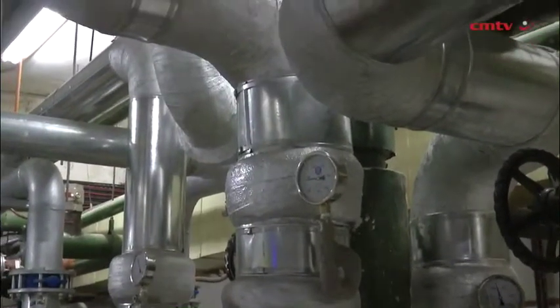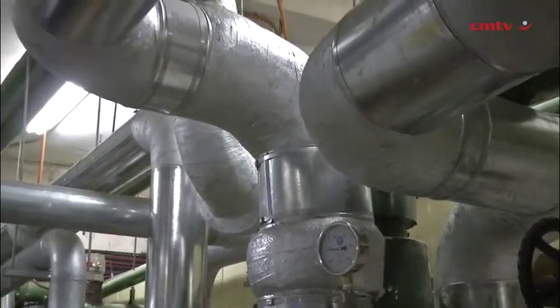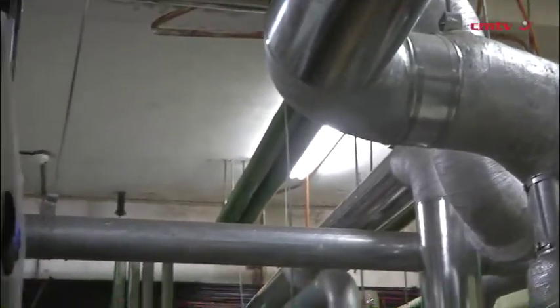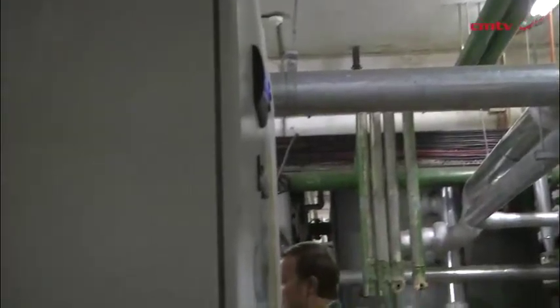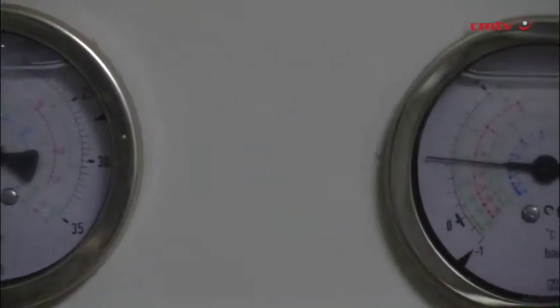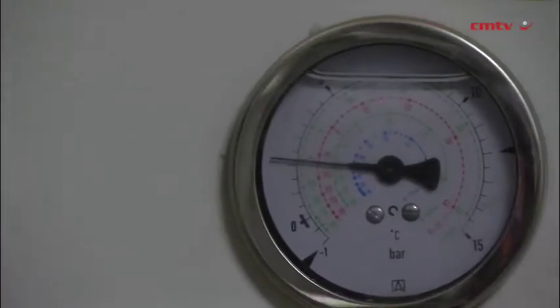So we looked at a heat recovery on the baseload chiller because the hospital has a 24-hour cooling load. So we knew we could recover heat 24 hours a day, 365 days of the year. The baseload chiller handles half of the cooling capacity of the hospital during the peak of summer. At the moment, on a cold day like today, it's reduced down to about 12% of the chiller capacity itself.